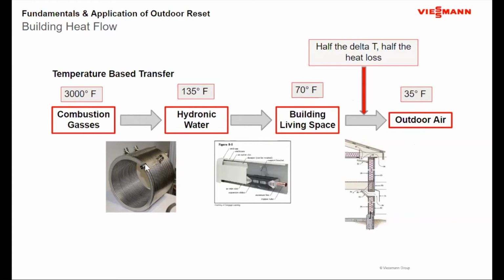Also over here, now let's jump back to the heat emitter. The hydronic water temperature inside the heat exchanger is lower. If I have a lower temperature here, my heat transfer from my combustion gases to my hydronic water becomes better. I pick up more sensible heat. And not written in here, but also if this is a condensing boiler and I start to drop the water temperature, now I give the boiler a better opportunity to condense. So when we start to look at balancing the heat flow in the building, really our best option is to be able to change that water temperature, because by changing that water temperature, I will change the performance of my boiler, change the performance of my heat emitter, stay balanced, stay comfortable.